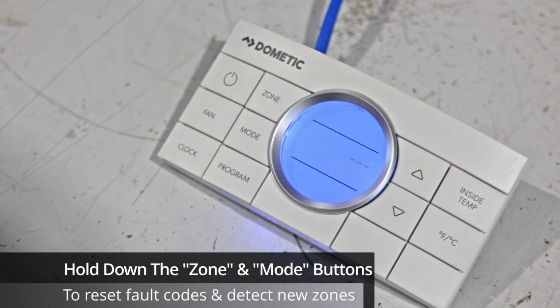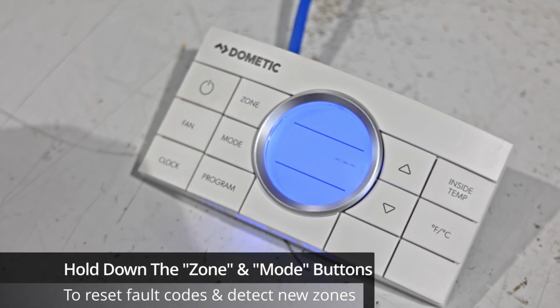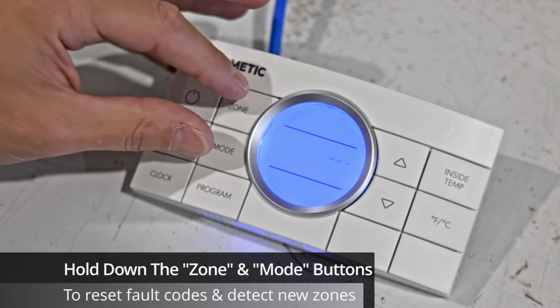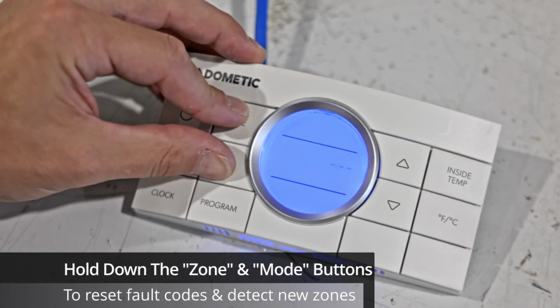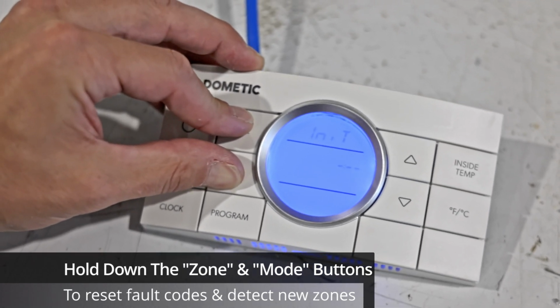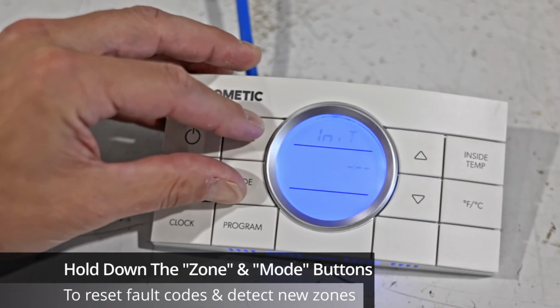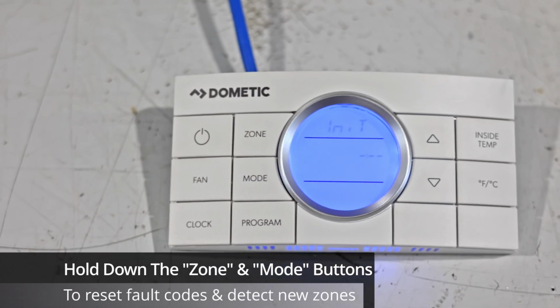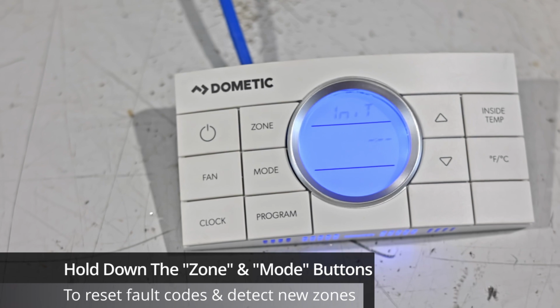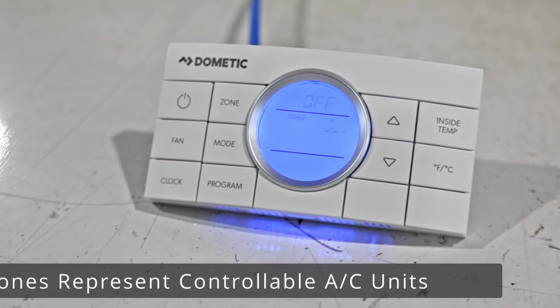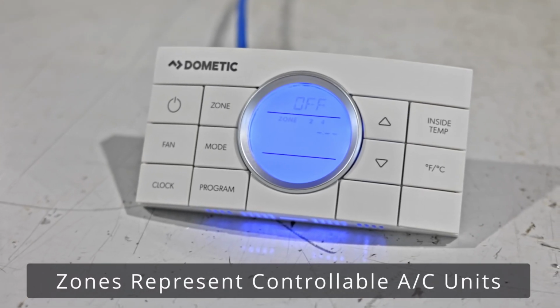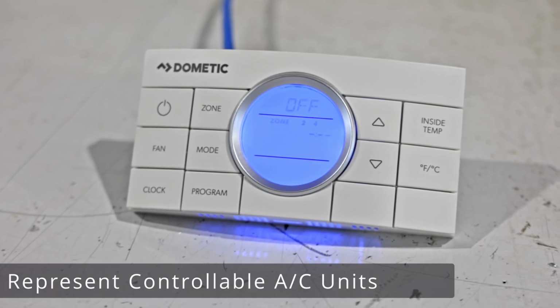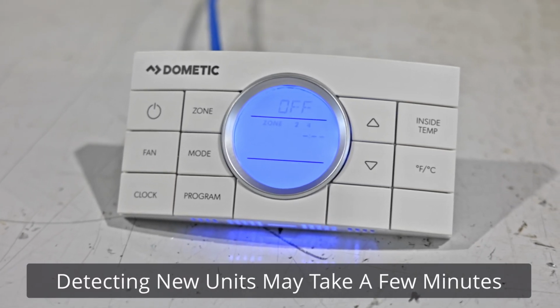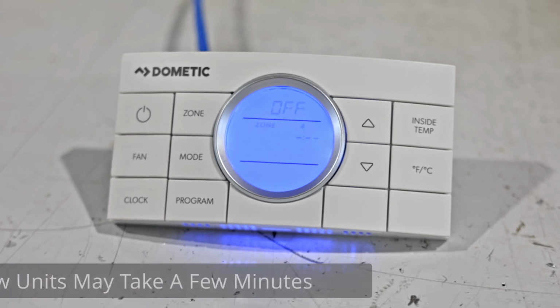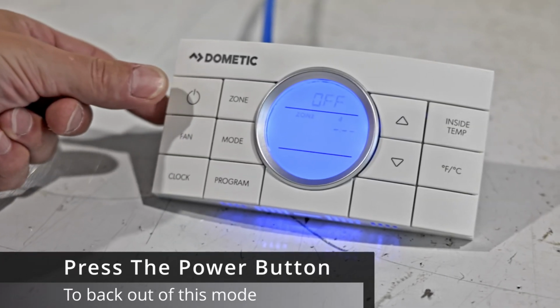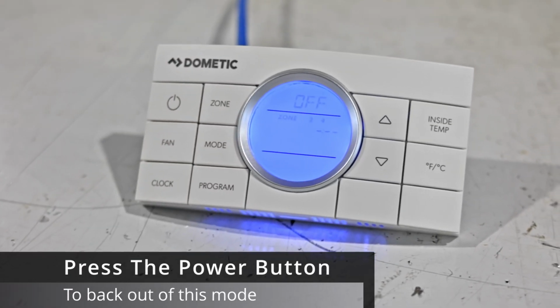If you need to reset a fault code or detect new units, with the panel turned off, you can hold down the zone and mode buttons until the display changes as shown here. This will clear any of your fault codes and allows the panel to detect any new connected zones. Each zone on the panel will represent a controllable air conditioning unit. However, detecting new units may take a few minutes. Once this is done, press the power button to back out of this mode.